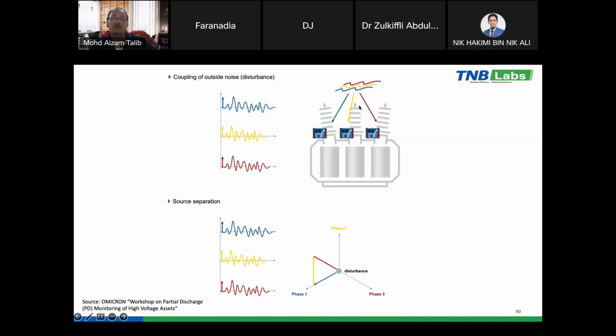What happens when we have noise? When we have outside noise or disturbance, all the measuring instruments will pick up almost similar amplitudes. So when we plot these three different signals, here we have phase 1, phase 2, and then phase 3 goes to the center. So by the different clusters at different positions, we are able to differentiate the PD activity in the transformers.